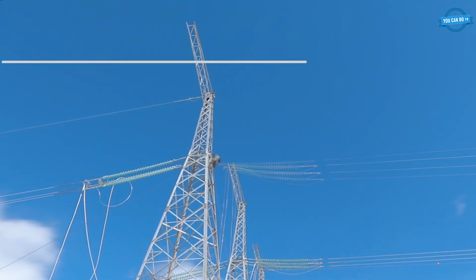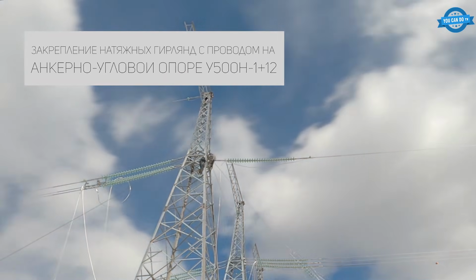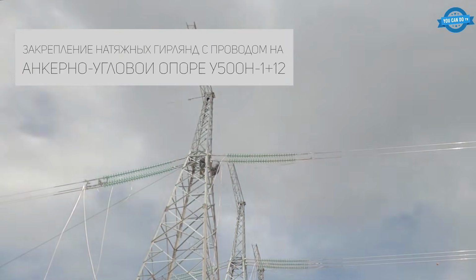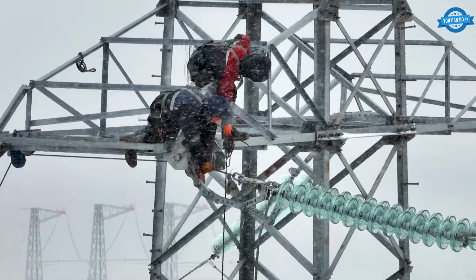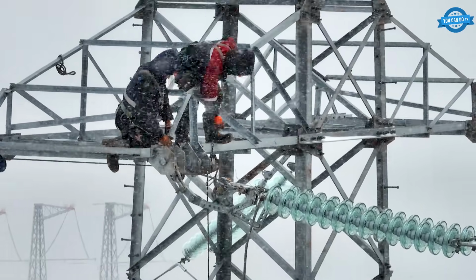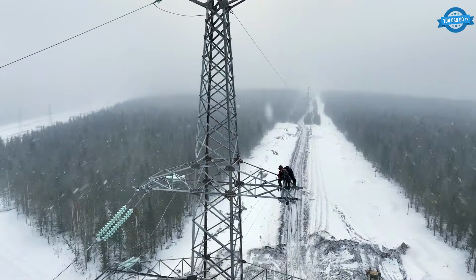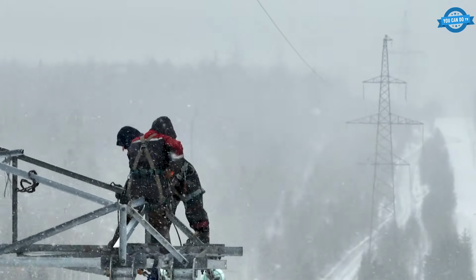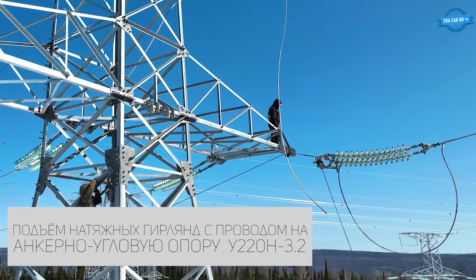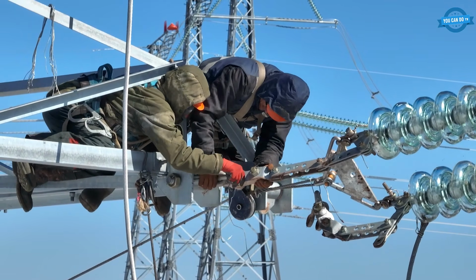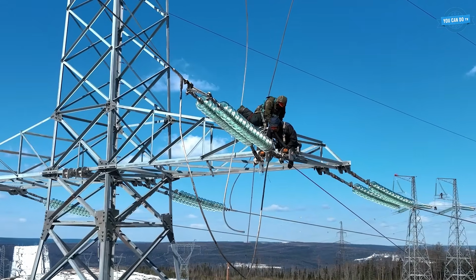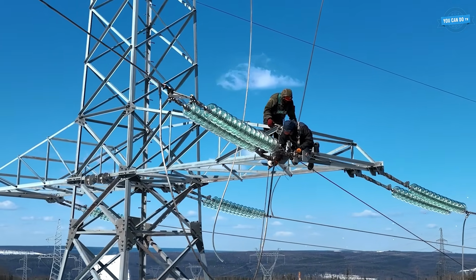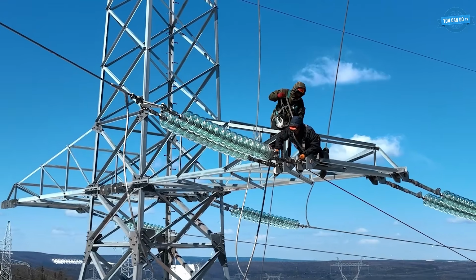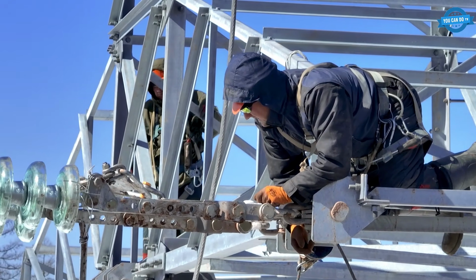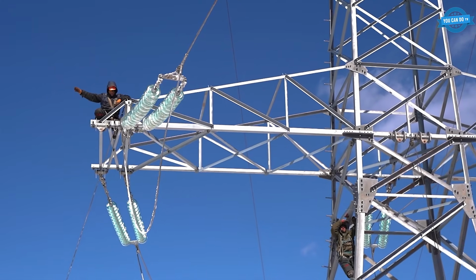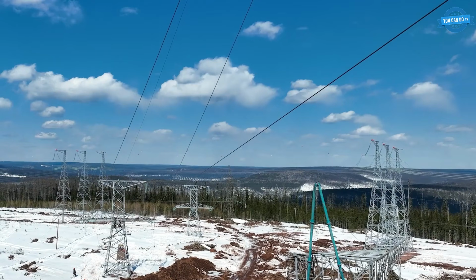Day 3 restores the original 220 kilovolt span. Days 3 to 5 dismantle the temporary metal tower U220 N2.2+14 used during the work. Day 5 installs new conductors and jumpers on the 220 kilovolt line with hydraulic press crimping of tension clamps and assembly of insulator garlands on the new anchor corner tower. Day 6 completes the job and re-energizes the 220 kilovolt line.